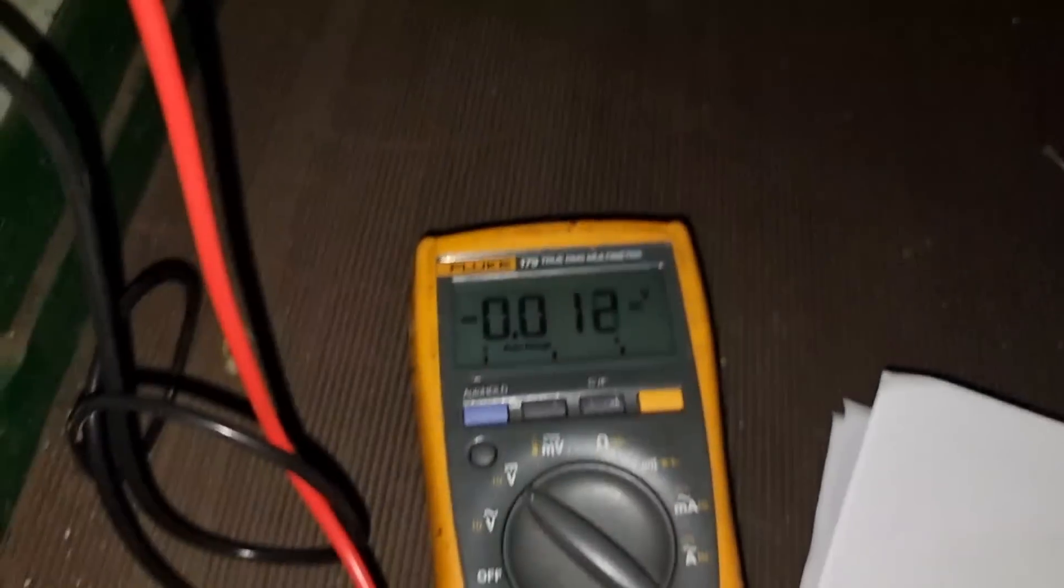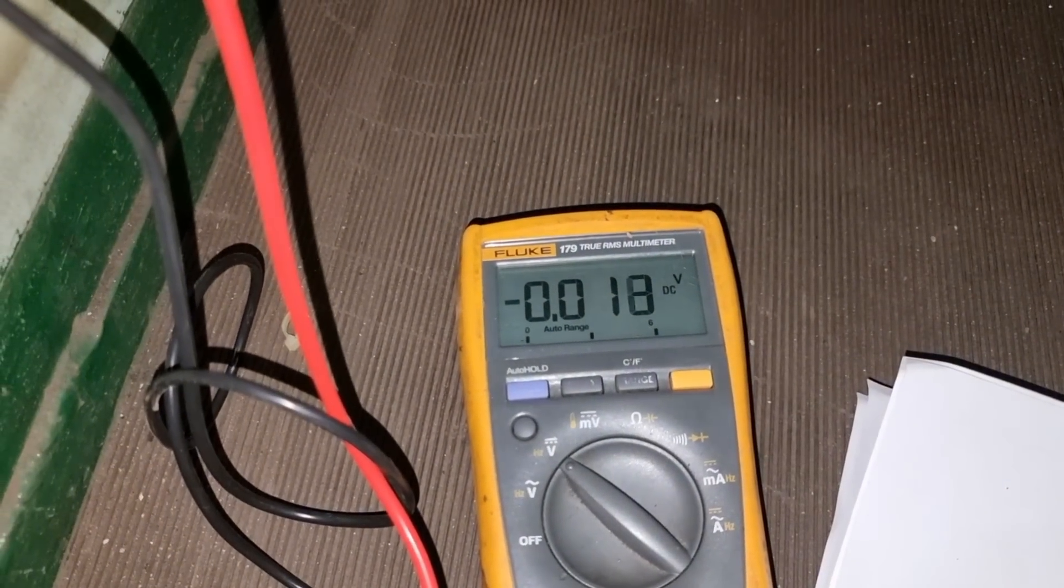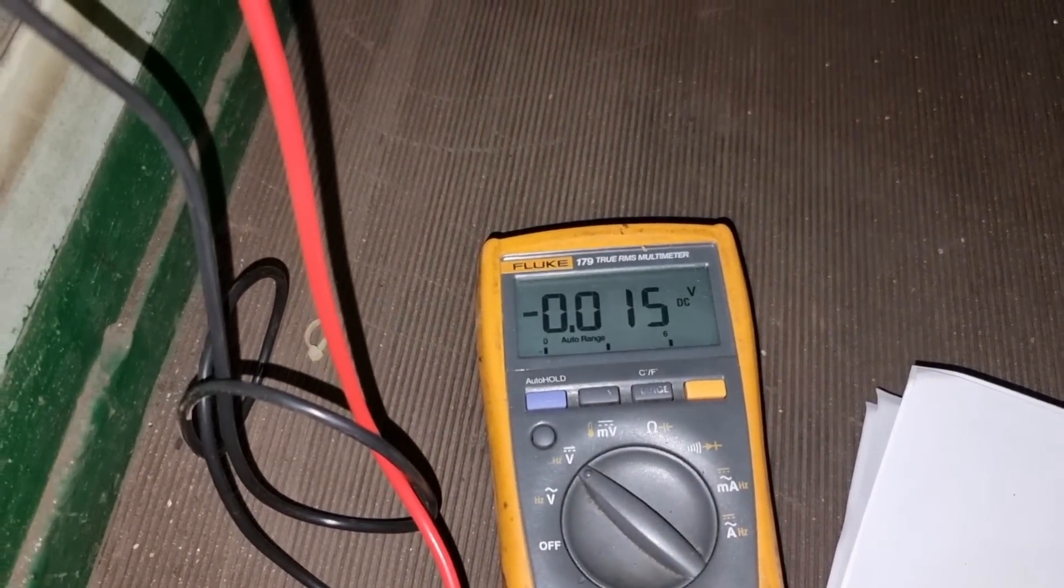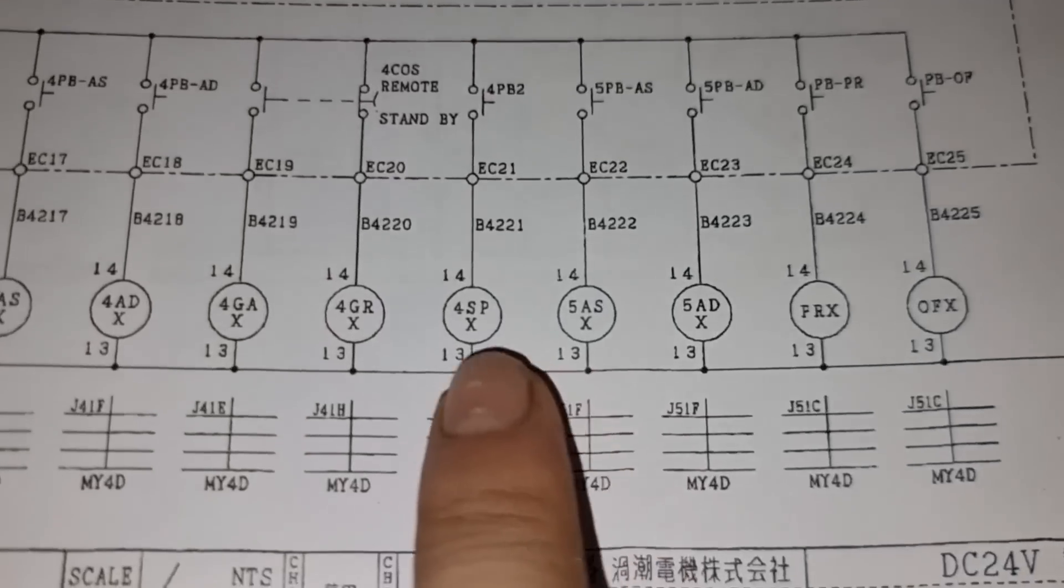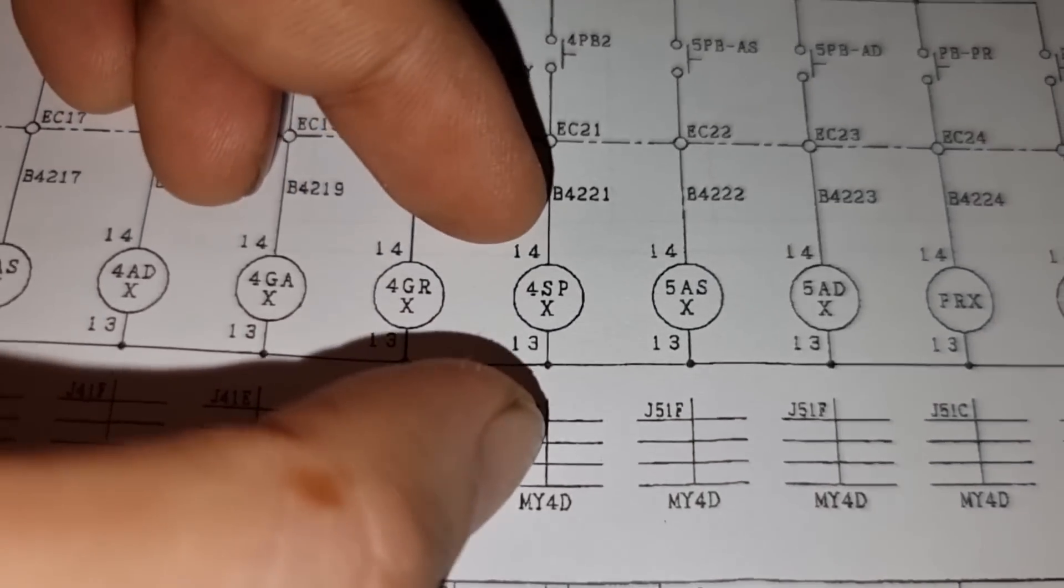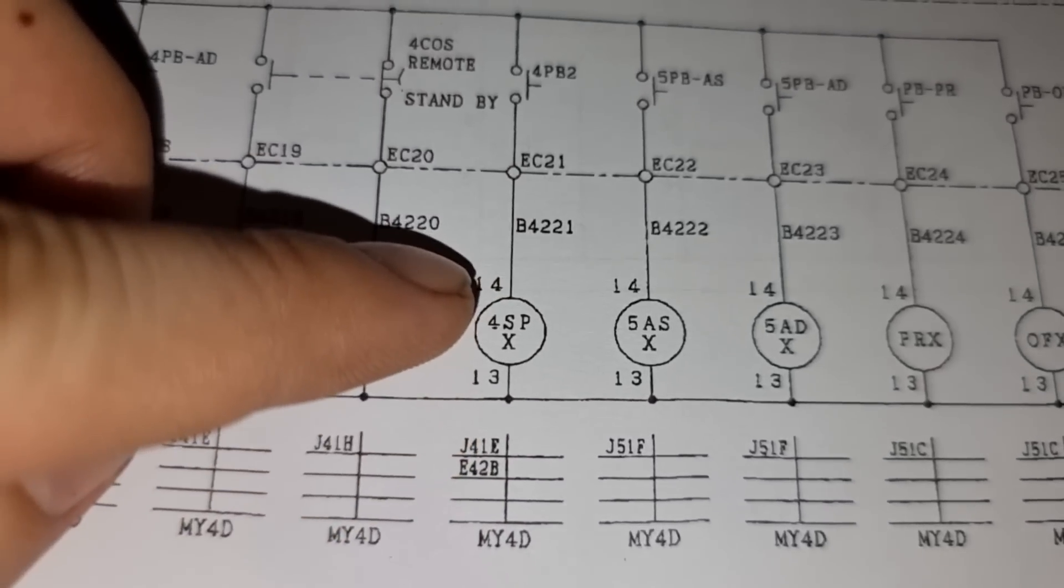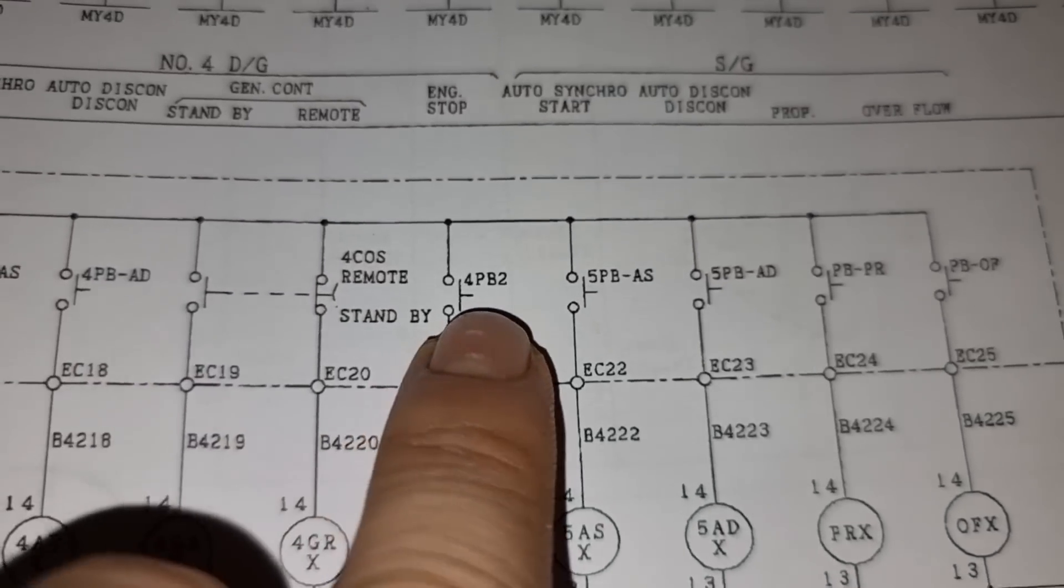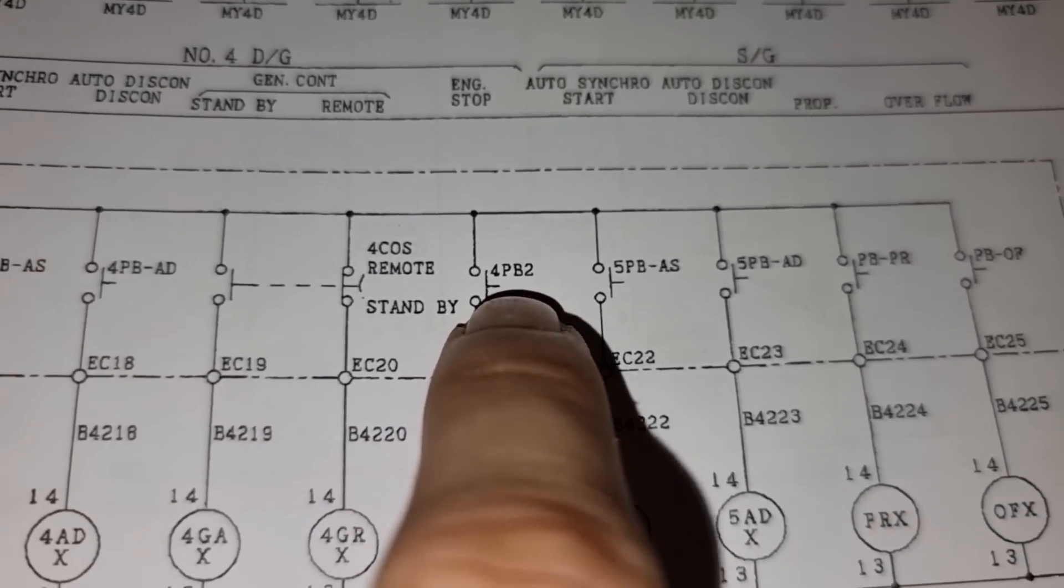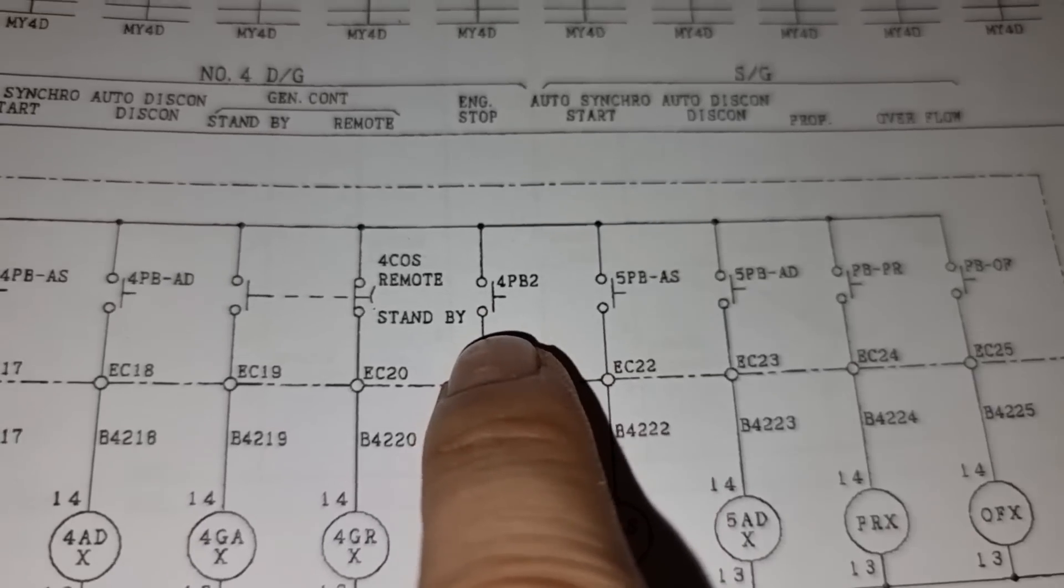And then I ask the engineers to do the stop command again onto the generator number 4. So finally, we are not getting 24 volts on the 13 and 14. So it means that this 4PB2 is not closing.